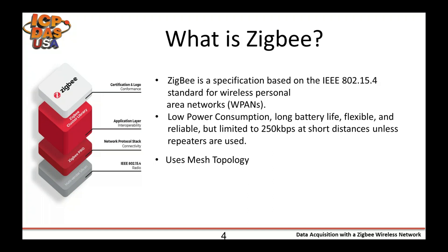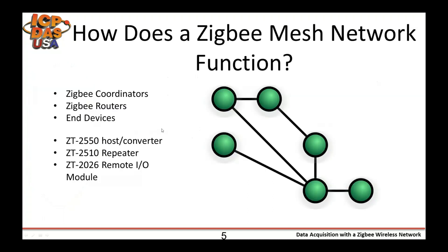ZigBee has most recently found a lot of applications in personal home automation systems, but for our purposes we will be focusing on its industrial applications, particularly in a factory setting. The advantage of a ZigBee network is that each device consumes relatively little power. The trade-off is that data transfer is limited to 250 kilobits per second. ZigBee signals are also limited to 100 meters line of sight unless you're using a repeater or a higher-powered transmitter. Some of our modules, the ZT-2060 for instance, offer a higher transmission range.